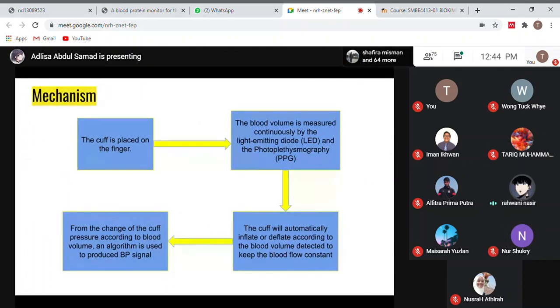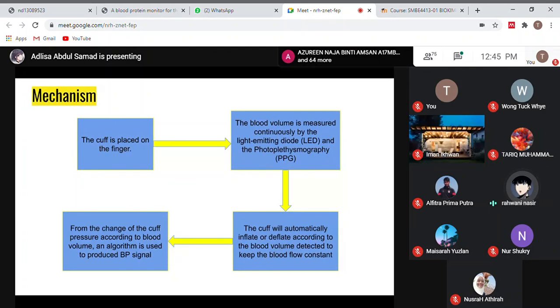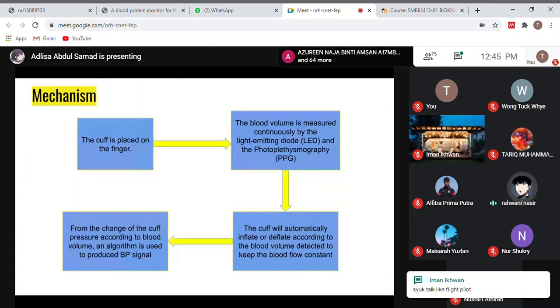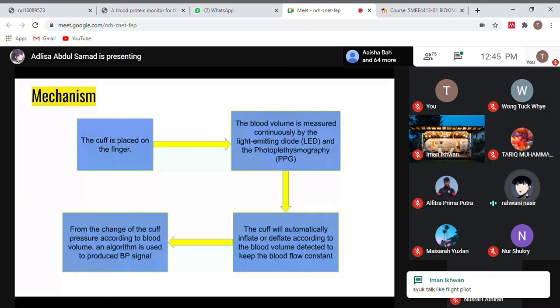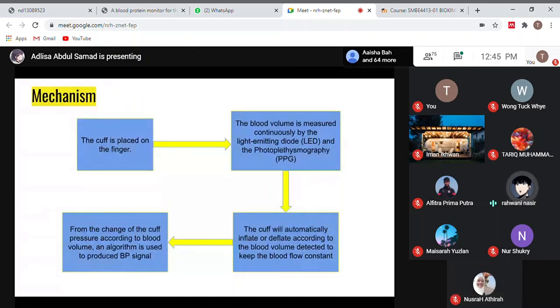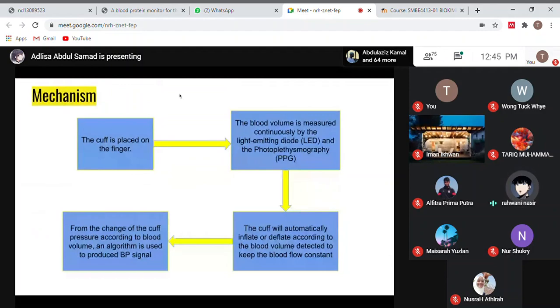For the mechanism of the volume clamp method, first the cuff is placed on the finger. After that, the blood volume is measured continuously by the light emitting diode or LED and the photoplethysmography PPG sensor. After that, the cuff will automatically inflate or deflate according to the blood volume detected to keep the blood flow constant. From the change of the cuff pressure according to the blood volume, an algorithm is used to produce the blood pressure signal.